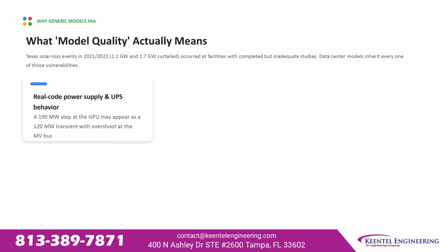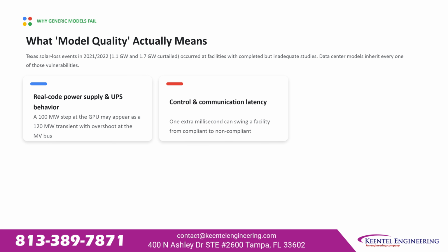Texas solar loss events in 2021 and 2022, 1.1 gigawatts and 1.7 gigawatts curtailed, occurred at facilities with studies that were completed but inadequate. Data center models inherit every one of those same vulnerabilities. 6 things separate a real model from a generic one: real code power supply and UPS behavior. A 100 megawatt step at the GPU may actually appear as a 120 megawatt transient with overshoot at the medium voltage bus. Control and communication latency.